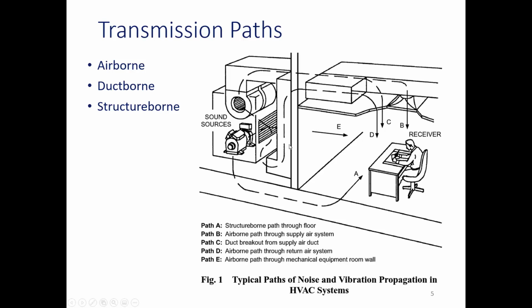So remember, the speed of sound was 1,125 feet per second, and a typical HVAC system can have a pretty wide range, but say that 1,125 would be a good middle-of-the-road number, but it's not feet per second, it's feet per minute. So the sound is traveling roughly 60 times, plus or minus, as fast as the air is moving. So it really doesn't matter which direction that air is moving.